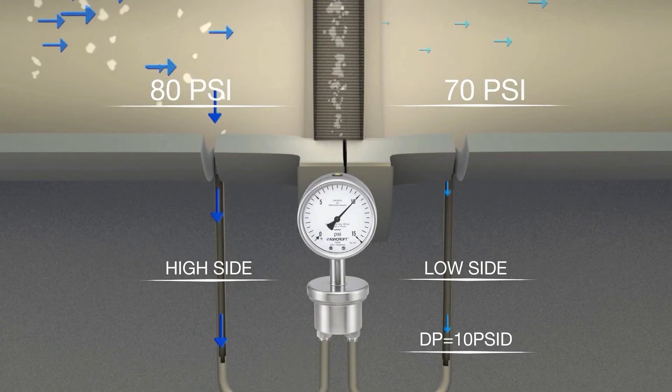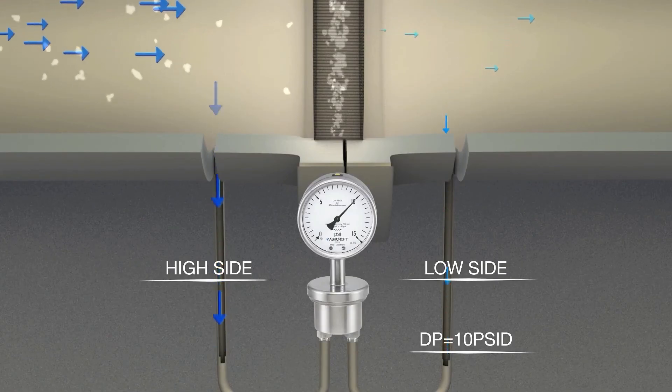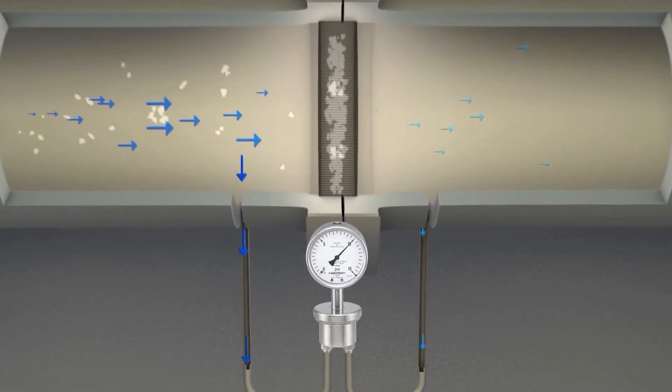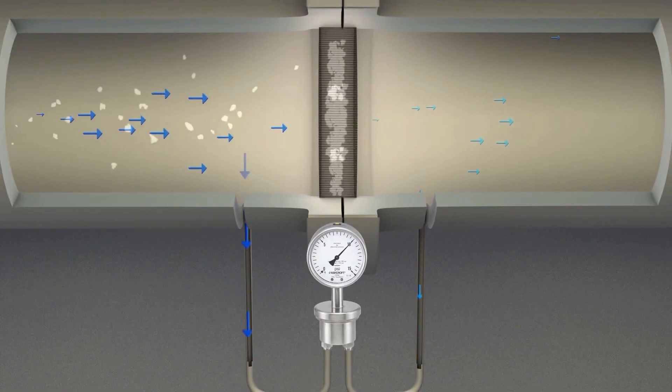The second is the instrument's ability to contain the static pressure, which is simply the pressure in the line while the differential pressure remains the same. A higher line pressure may require an instrument rated for higher static pressure.